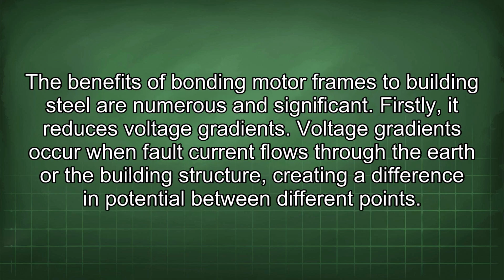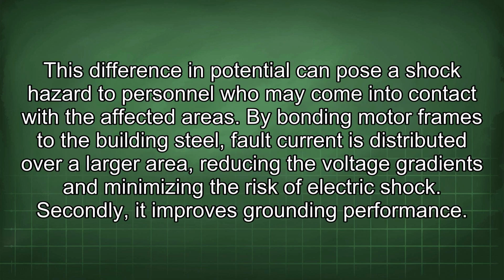The benefits of bonding motor frames to building steel are numerous and significant. Firstly, it reduces voltage gradients. Voltage gradients occur when fault current flows through the earth or the building structure, creating a difference in potential between different points. This difference in potential can pose a shock hazard to personnel who may come into contact with the affected areas. By bonding motor frames to the building steel, fault current is distributed over a larger area, reducing the voltage gradients and minimizing the risk of electric shock.